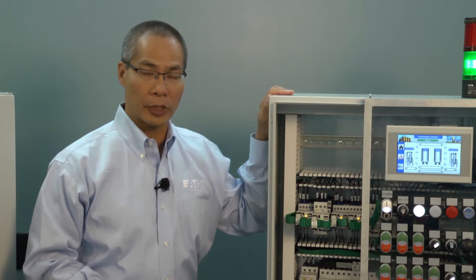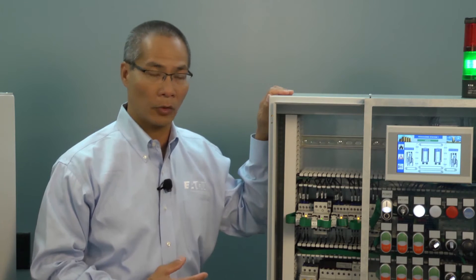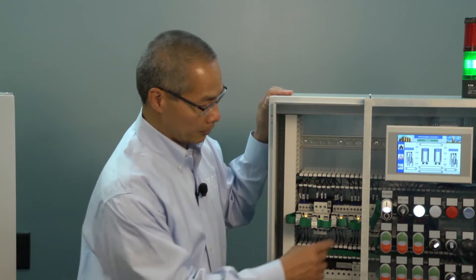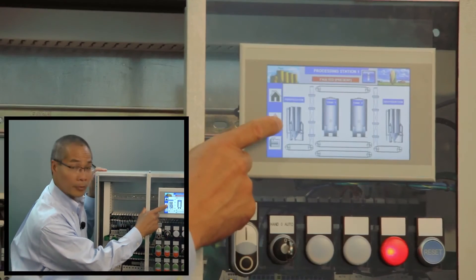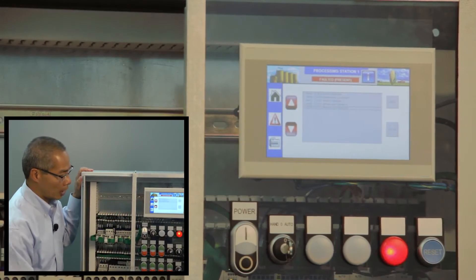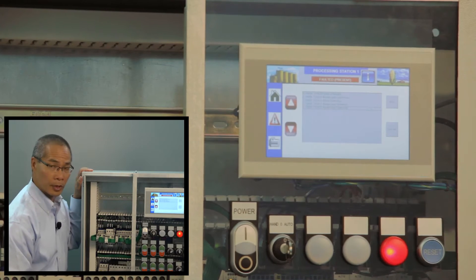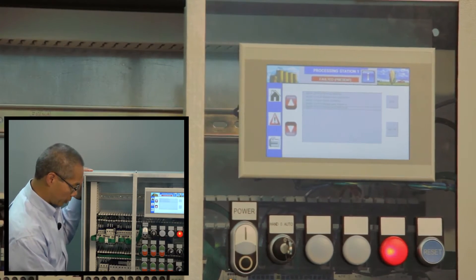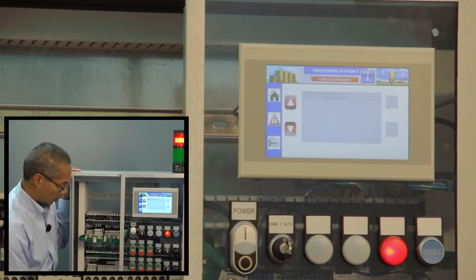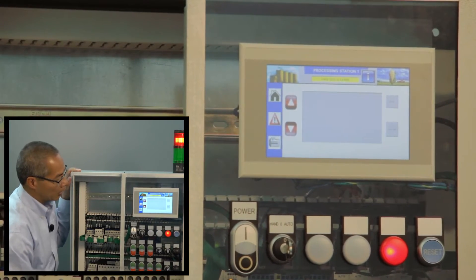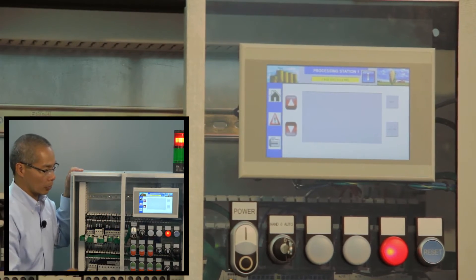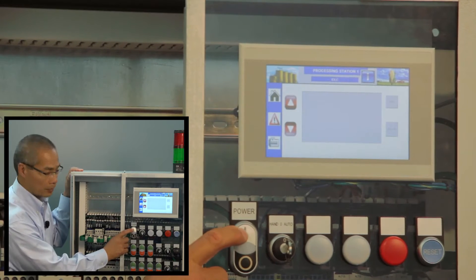One of the other benefits of using SmartWire DT is the enhanced diagnostics that you can get over the system. For example, if something were disconnected or turned off, I can monitor that information over the network and show it on my touch screen. I've set up an alarm page here that tells me exactly where those trouble areas are. I can then go in and make those corrections by reconnecting the devices, resetting my tripped manual motor protector units, and as the faults are fixed, the errors will go away. I would reset the device and then restart my system.